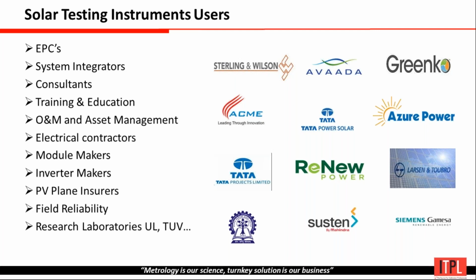You can test a minimum of 120 to 150 strings in a single day, 100%, if your engineer is working perfectly. So for testing a 1 megawatt plant, I think around 10 to 15 days you can complete the work, because you also have to account for days with less radiation, rainy season, or other things that might happen. So we take it as 10 to 12 days.